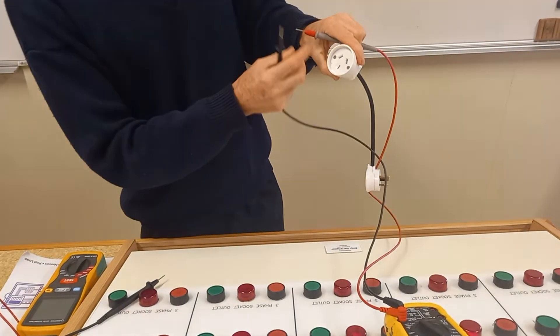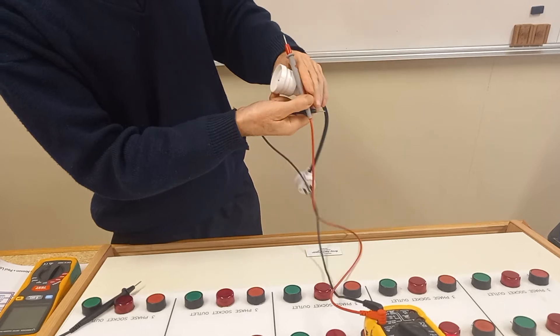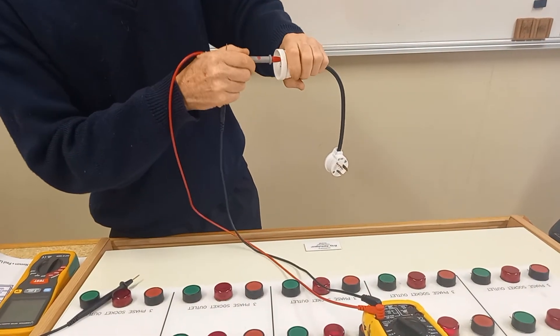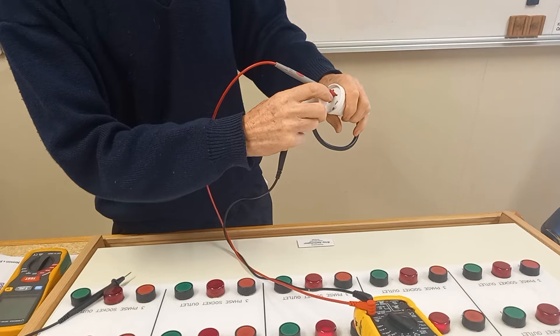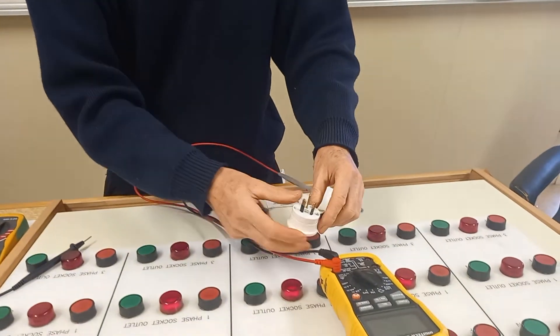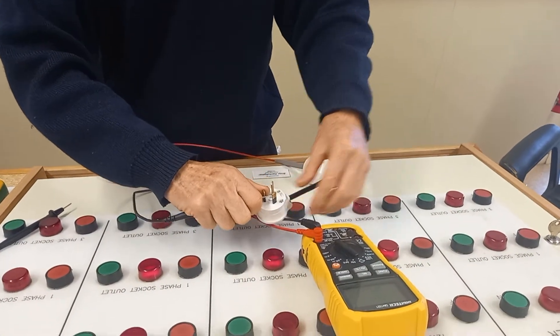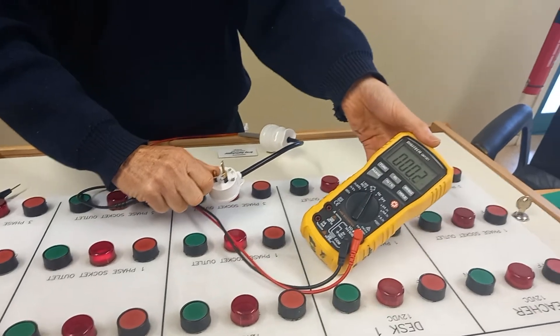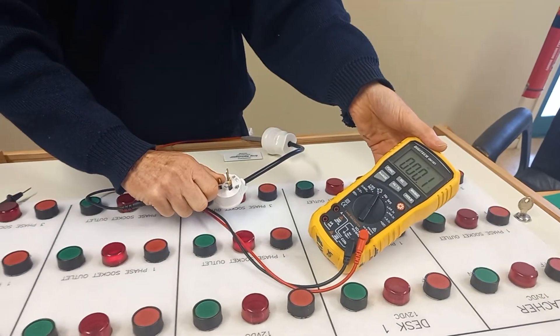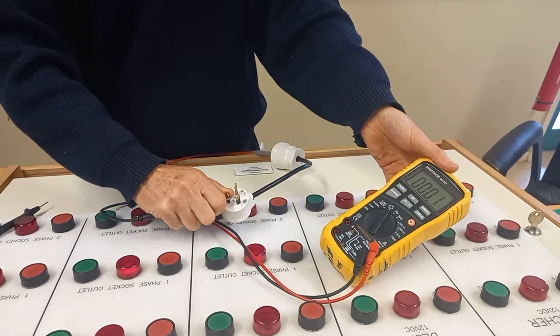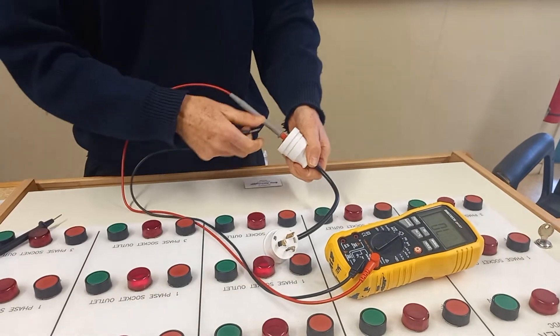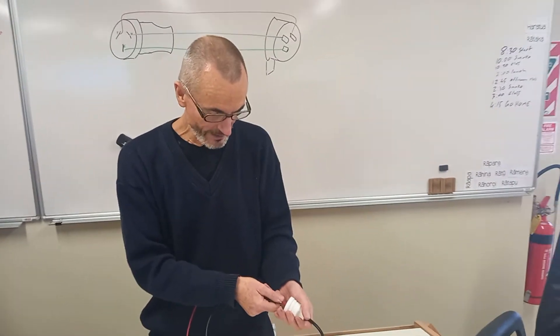There is my phase terminal there. I go to plug that in there. There is my phase terminal there, I expect low resistance and I'm getting it: 0.1. So that's proved continuity and it's also proved polarity.